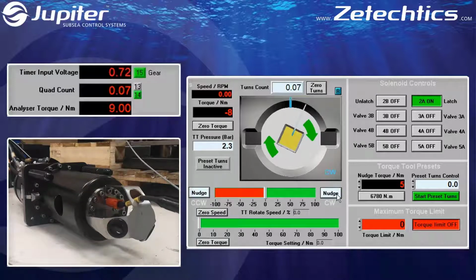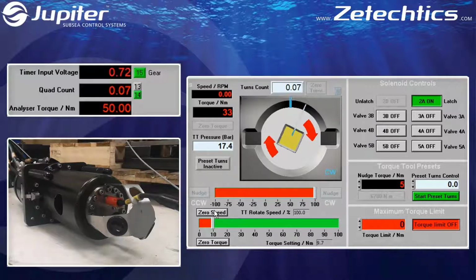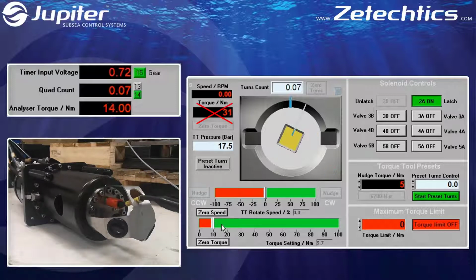Nudge the tool clockwise to take up the slack. Apply pressure in stages, opening and closing the flow valve in between each step. The auto calibration applies 100% flow, so the same should be applied when testing. Only monitor the analyzer torque reading. As a calibration has not been performed, the tool feedback cannot be relied on yet.